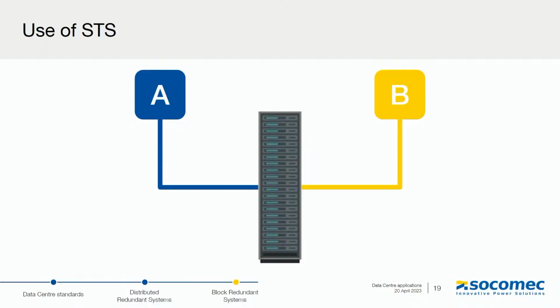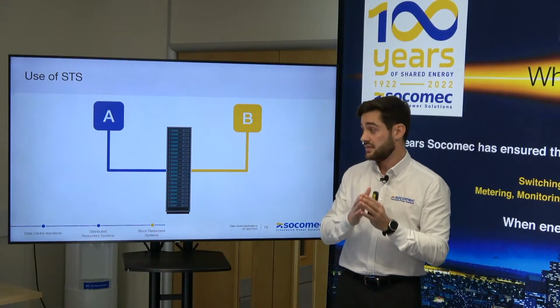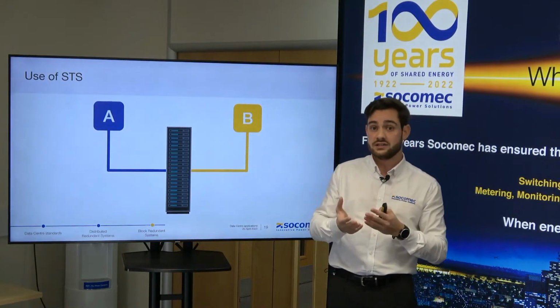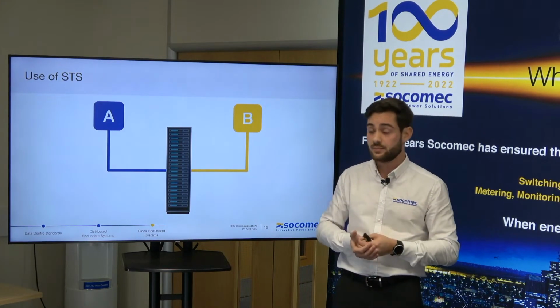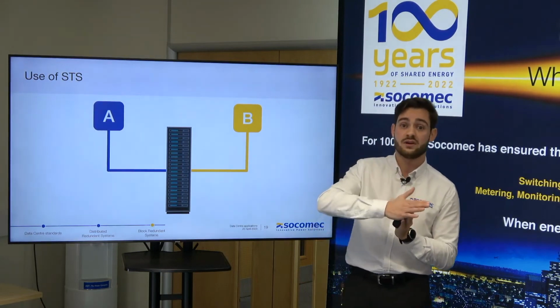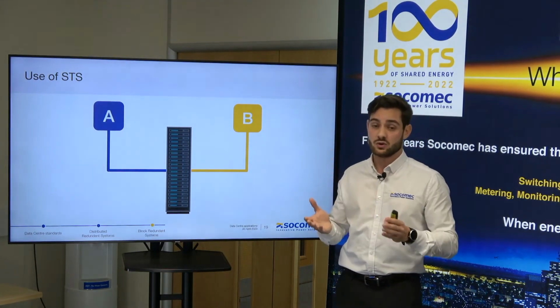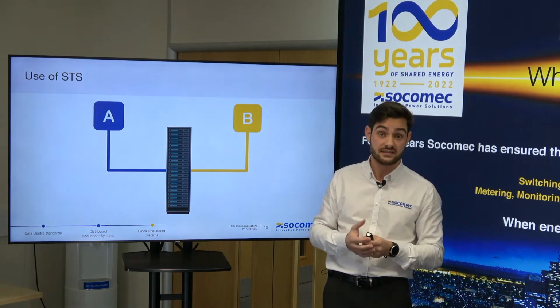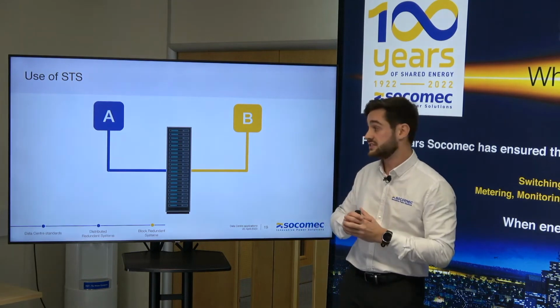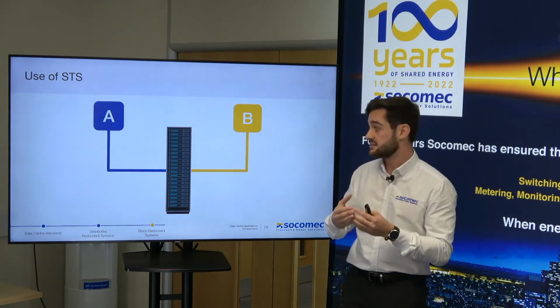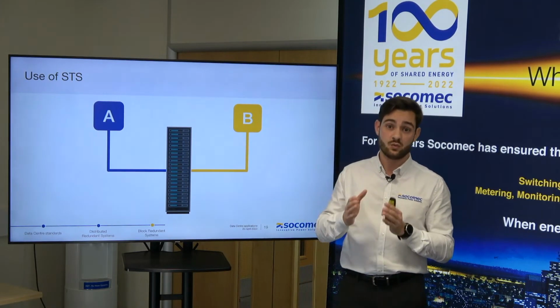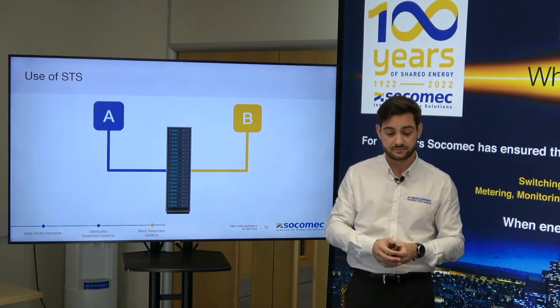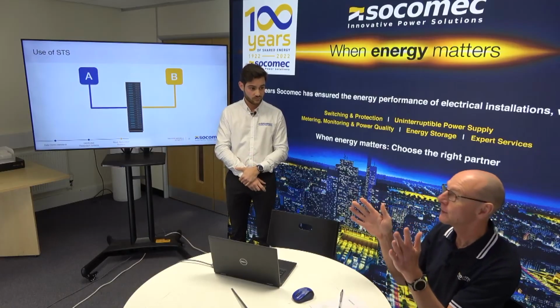So basically an STS is a product that is designed to take 2 power supplies, mainly coming from 2 UPS systems. And then in case of failure on one power path, so imagine you're out of tolerance on the voltage or the frequency, for example, the STS will pick that up and then transfer the load as fast as possible to the secondary path. As long as the transfer is done within 20 milliseconds, there is no impact for the load because of the ITIC curve. The ITIC curve says, black on white, that all IT equipment can work at 0 voltage for up to 20 milliseconds. But obviously STSs, if you've got synchronized power paths, are going to transfer within 3 to 5 milliseconds. Yeah, so even faster. Well within the ITIC curve, but obviously the limit is 20 milliseconds.